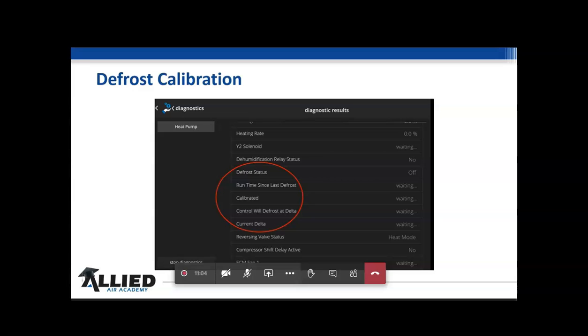So I can look at this and say, okay, it's been 90 minutes since I've run, or 2 hours. It's been 2 hours since I had a defrost last. But the two I want you to really look at is the current delta, and the control will defrost at delta. And I'm going to take a look at this picture so I can describe for you what is on my stat. So my control will defrost at delta is 0.6 Fahrenheit. Okay. This is when it warmed up. In the morning, it was a little different. And I'll talk to you about that as well. But in the morning, it was a little different. And the current delta was 3.4 degrees. That's between the two sensors. My unit was off when this was happening.